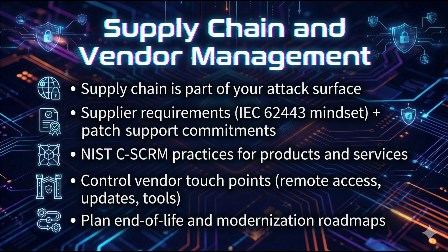Remote access should be time-bound and monitored. Software and firmware updates should be validated and staged. If possible, request a software bill of materials, SBOM, or at least component transparency, so you can understand exposure when new vulnerabilities are disclosed. Finally, plan for end of life.